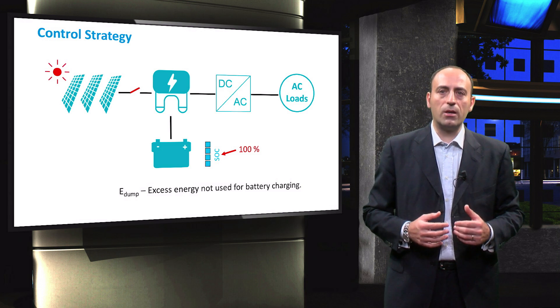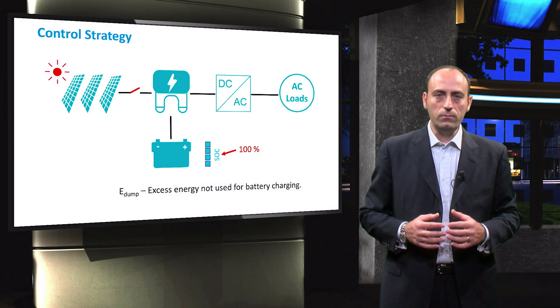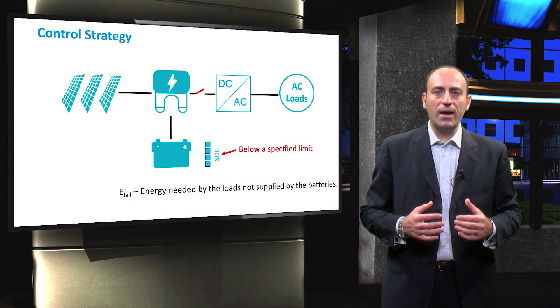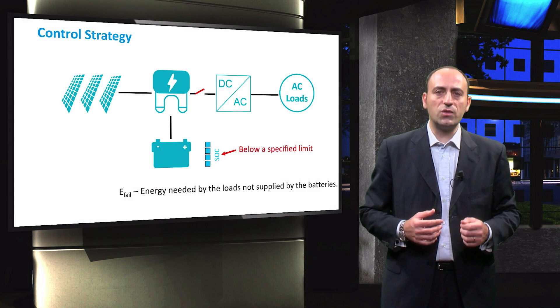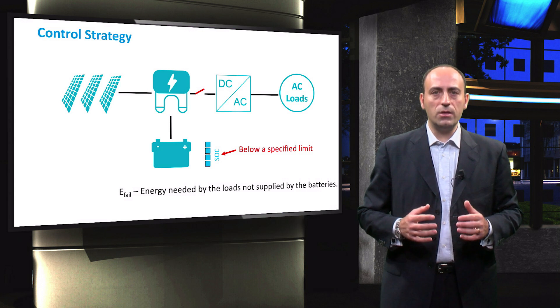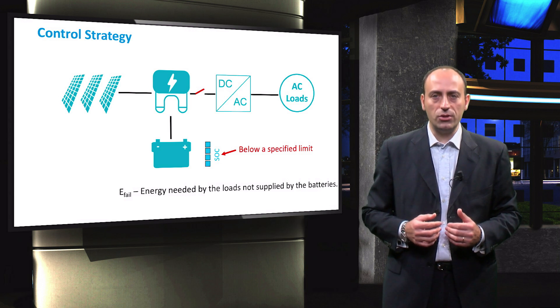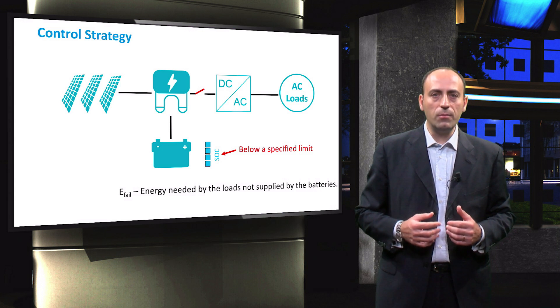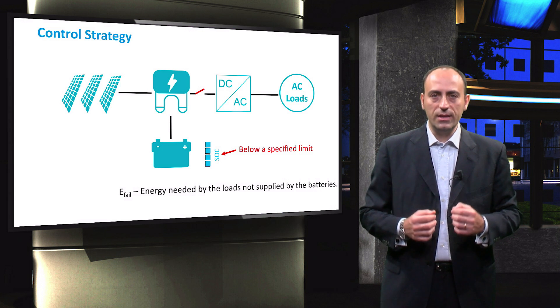In the control strategy algorithm, this means that the parameter E-dump is calculated. On the other hand, while feeding a load, when the battery bank SOC goes below a specified lower limit, the inverter side switch is opened. This means that the battery will fail to supply energy to the loads. In the control strategy algorithm, this means that the parameter E-fail is calculated.